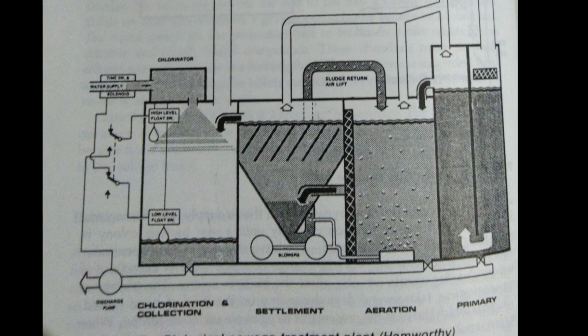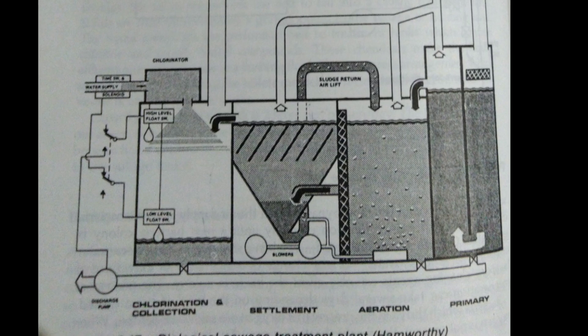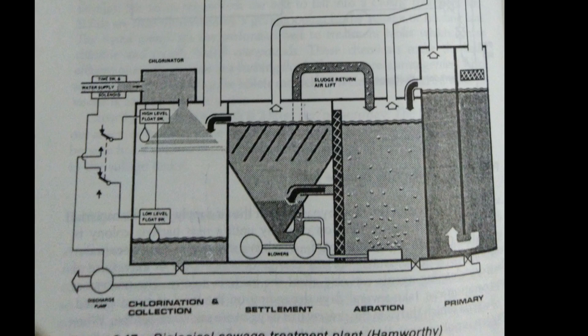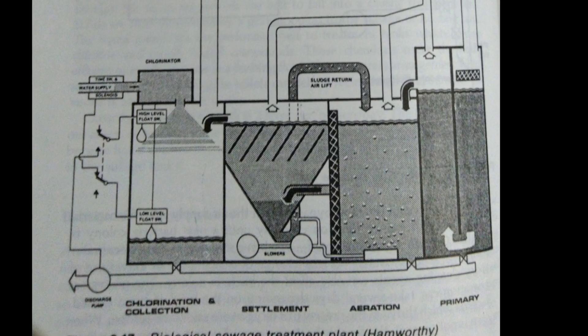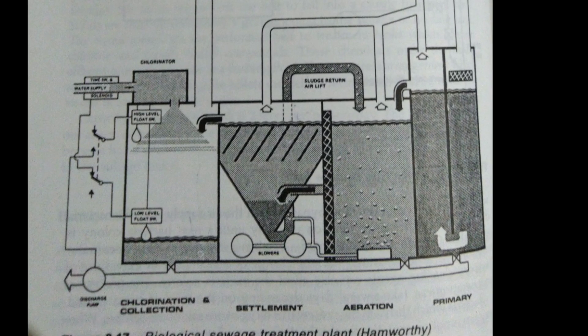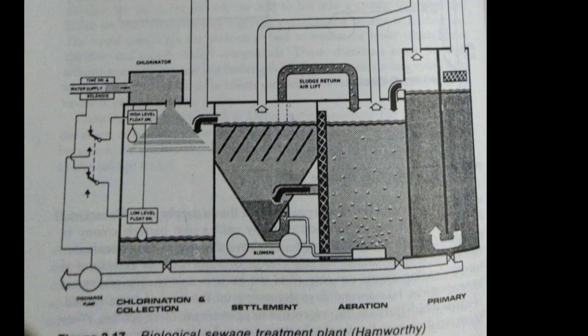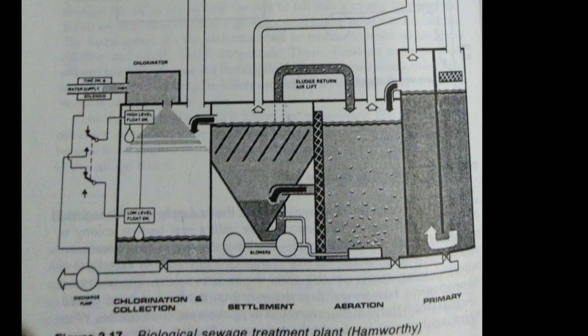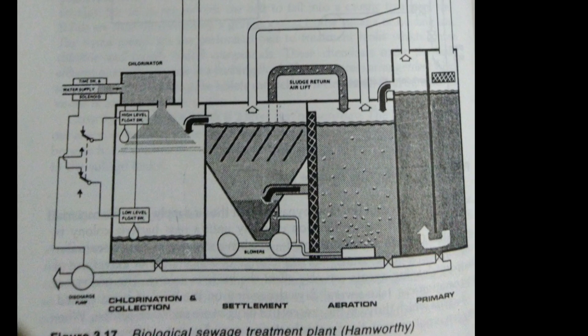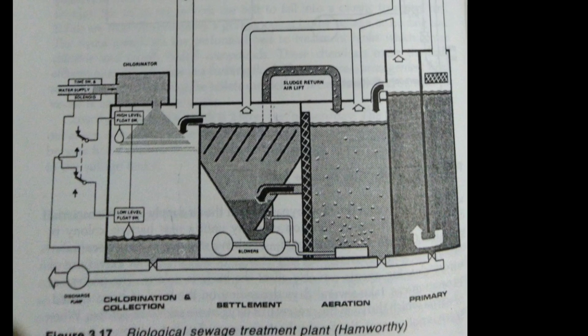After the settling stage, water flows back to the chlorination or sterilization chamber. While flowing through, it passes through pipes with holes so it touches the chlorine tablets and gets chlorinated and sterilized. Sometimes you will also see UV lights — nowadays you'll find a small chamber with UV light to kill all microorganisms. The reason we do chlorination is to kill the bacteria we have created ourselves, so it doesn't affect the outside environment.